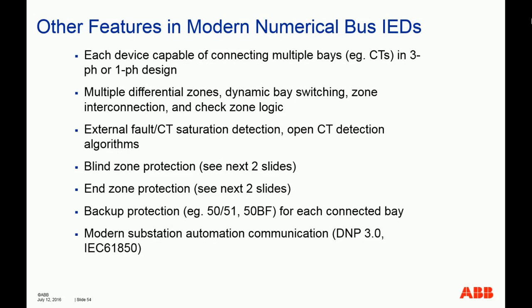Especially breaker fail protection really comes very handy, because think about it, for those types of double bus bar single breaker scheme, any CT, any breaker can be connected to either bus. How would you know which bus this breaker is currently connected to? If you use a separate, standalone breaker fail protection relay for each breaker, then you may run into trouble. You need to create some very heavily customized, convoluted logic to determine exactly which bus this very breaker is currently connected to.